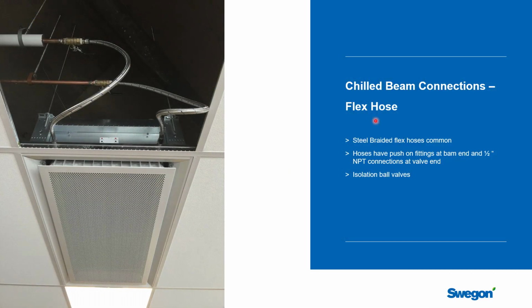So that's an idea of what beams are going to look like when you see them in the space. Let's start to talk about how they get piped up. So over here we have a 2-pipe beam application. Pretty common thing to see. You've got copper lines coming in, and then it's very common to see flex hoses used. This allows for adjustment as threaded rods are used to lower the beams into the ceiling grids. You can have that flex connection if you need to move the beams around a little bit. And a lot of projects have fire rated or stainless steel braided hoses connected to the units. And it's also very common to see some form of isolation, a ball valve or something, so that if this beam needs to be serviced or has any issues, you can isolate it from the main loop.